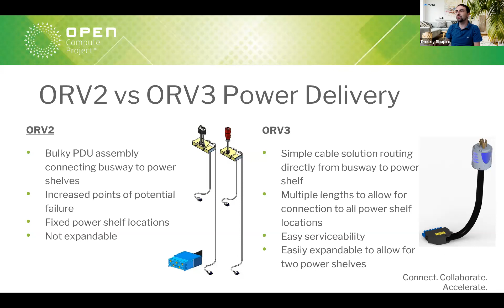Whereas on ORV3, we have a simple cable solution that skips the PDU and goes directly from the busway in the data center to the power shelf. You can have multiple lengths to allow for different power shelf locations anywhere within the rack. You have easy serviceability - just plug the cable, take it out of the rack, plug in a new one if needed, instead of disassembling an entire PDU. You can also expand it to have two power shelves within a rack, or just one as needed.